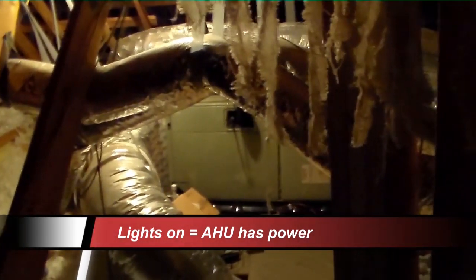You can see already that the damper lights are on, so the transformer feeding the damper just got power. Let's take a closer look at the air handler over there. You can hear the line set, the condenser is running, but no fan motor. And this fan motor was replaced a couple years ago. I remember that because I actually brought my son along for part of the job.